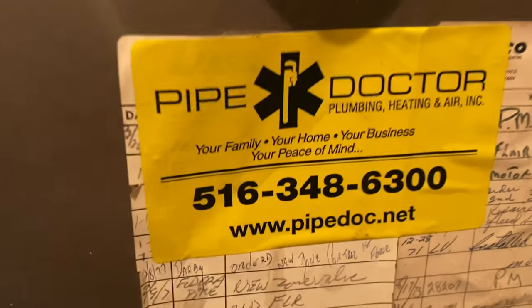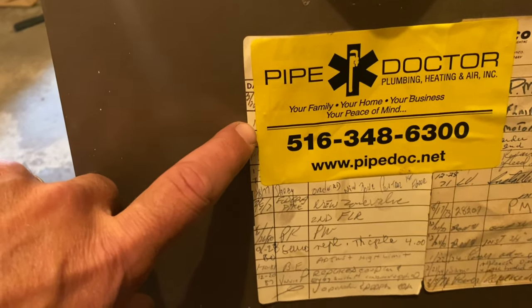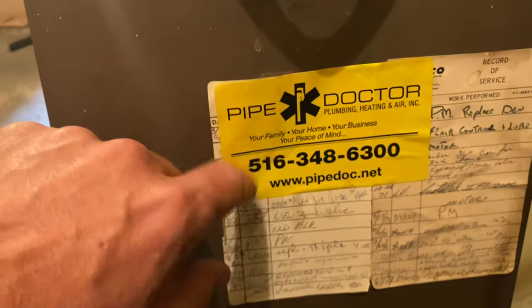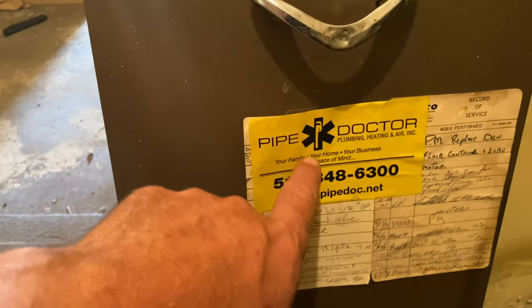Here doing an annual tune-up on this old Federal boiler. You can see the old LILCO service history dates from the early to mid 1970s. We were here last year and did a combustion test. The parts per million of carbon monoxide was 978 last year. Now we're over 3,000. I stopped it because at 4,000 it's going to go into sensor protection.